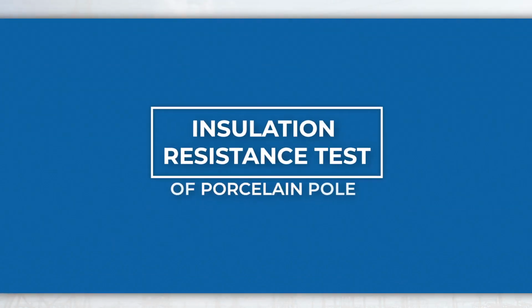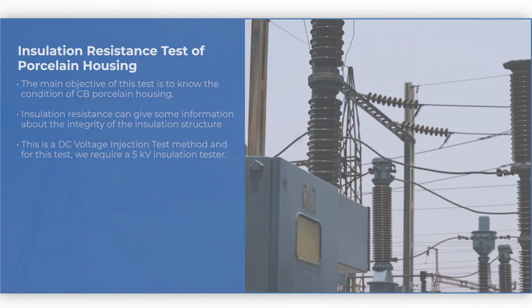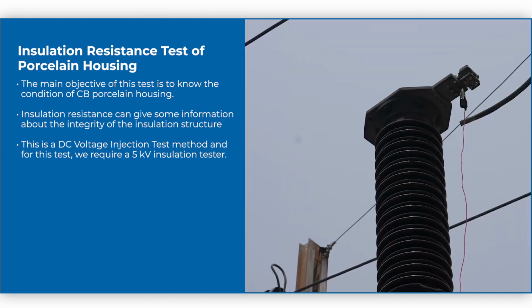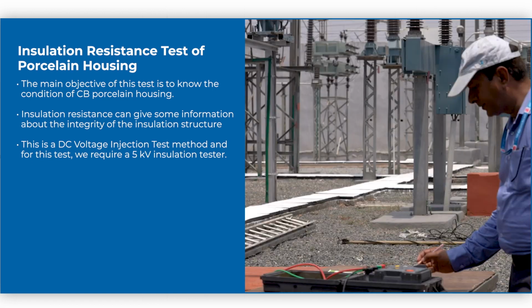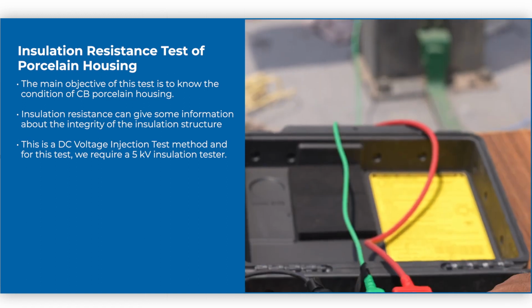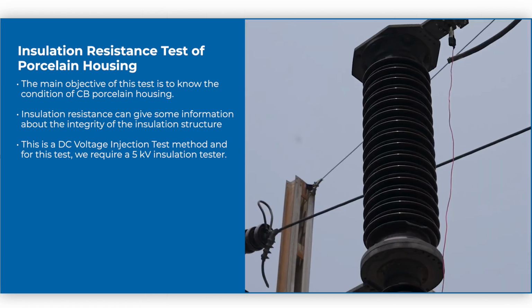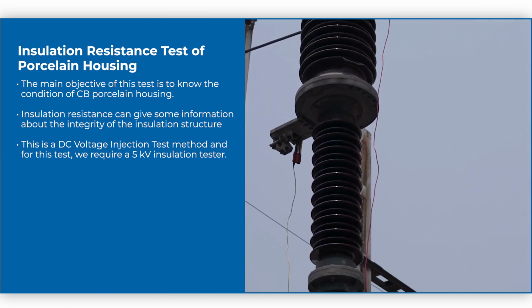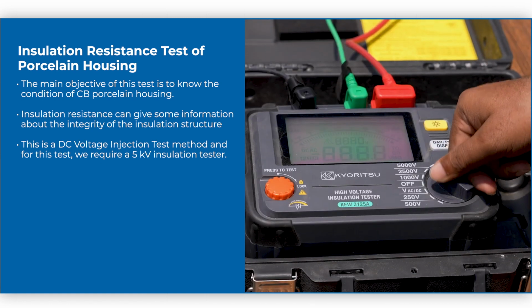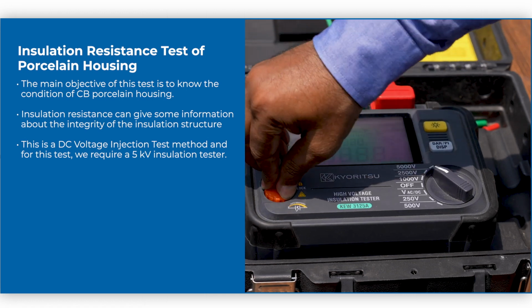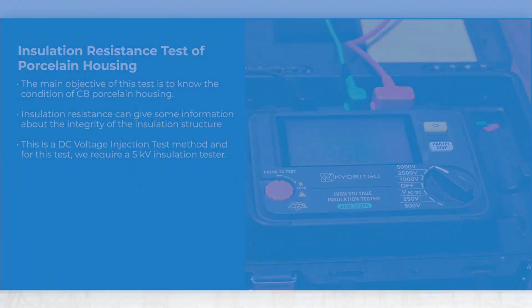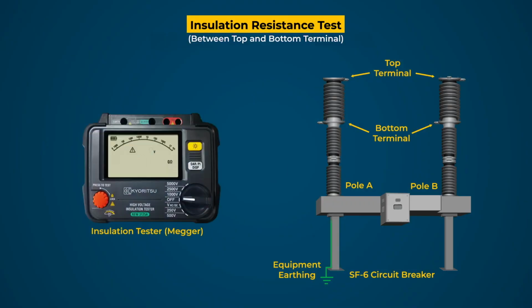Insulation resistance test of porcelain pole. The main objective of this test is to know the condition of CB porcelain housing. Insulation resistance can give some information about the integrity of the insulation structure. This is a DC voltage injection test method, and for this test, we require a 5 kV insulation tester. Steps for testing. First, open the connections of both pole terminal connectors. Here we are conducting the test between both terminals of pole when the main contacts are in open condition.